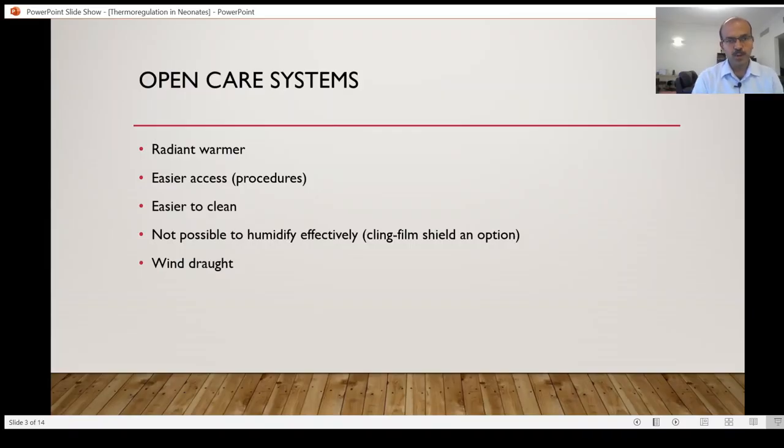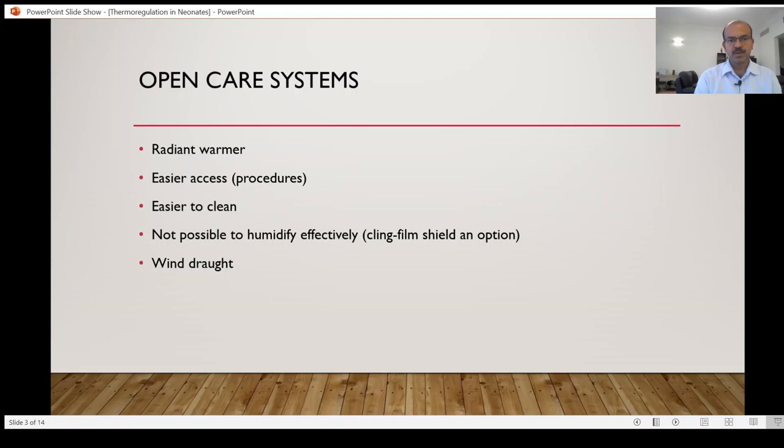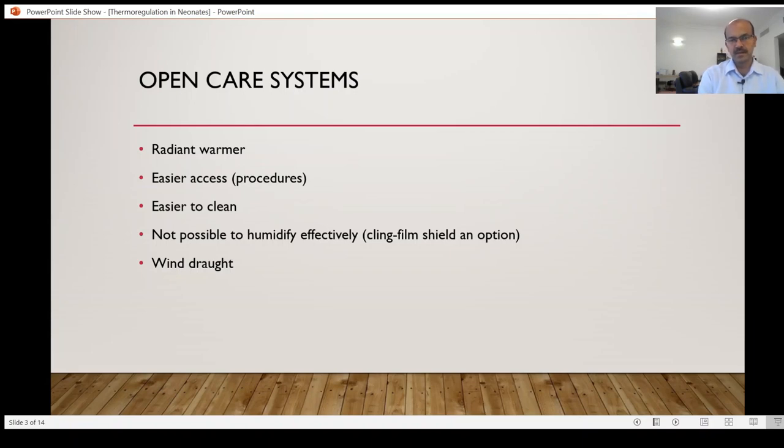When we come to open care systems, these are systems where the radiant warmer is used to provide heat. The main advantage is obviously to have easier access for procedures and they're easier to clean. It is not possible to humidify effectively in the radiant warmer.